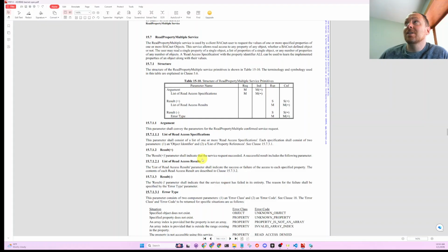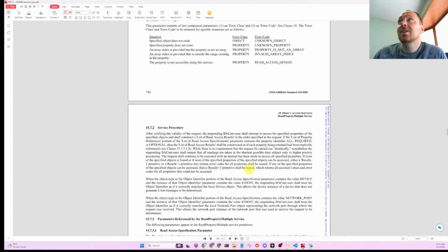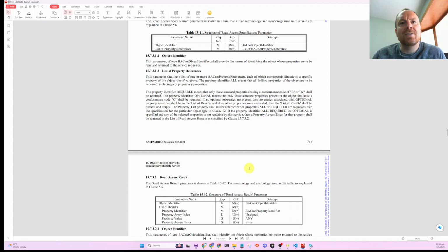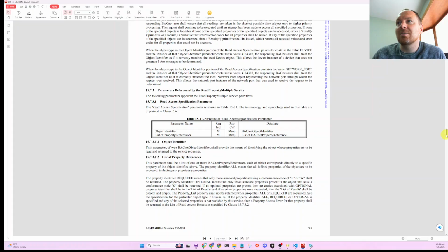So I had to build some kind of special process of only doing 25 points at a time. I think we even talked about this on the BACnet read multiple video. It has to do with how many bytes of data the BACnet device can handle. So whatever. I think it's kind of cool, maybe we should just glance at this because it's not bad practice.